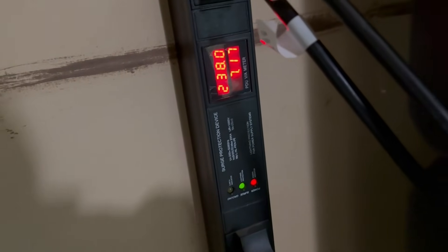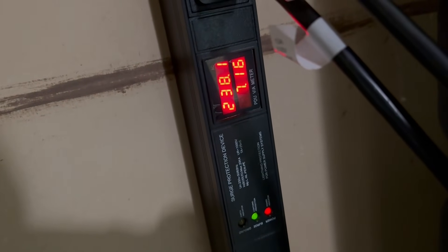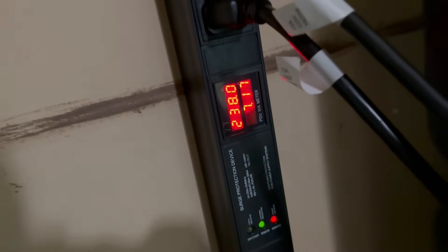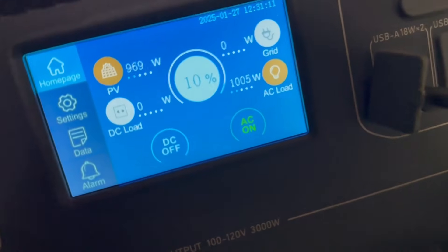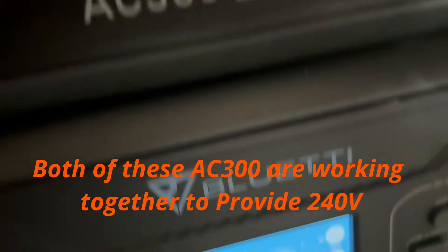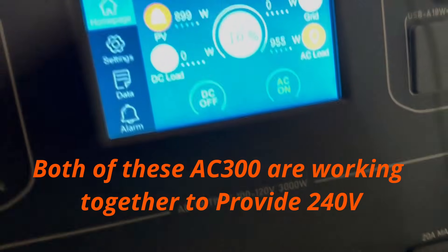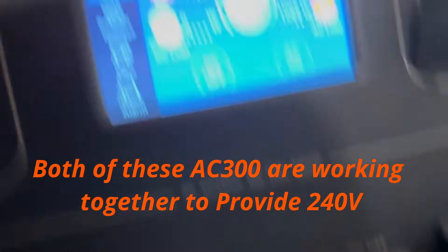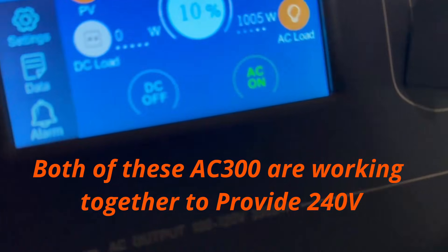Here's the power consumption in one of them. So this one is hooked up to this PDU. It's pulling about 7 amps, 238 volts. And the other one here. Now, this thing's in split phase, so it's actually about 1900 watts.